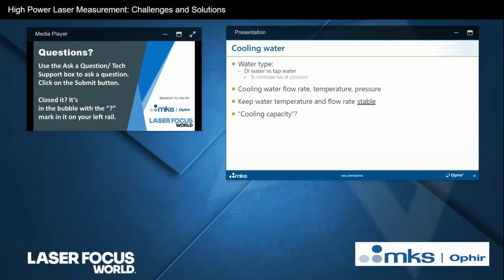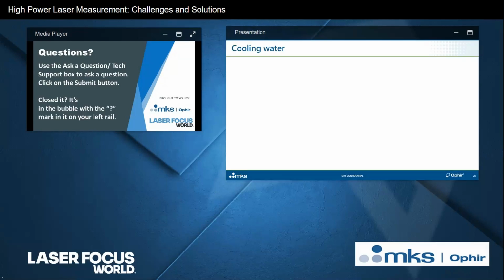I mentioned corrosion. I should just mention that Ophir offers a corrosion-proof sensor in which only copper and non-metallic materials come in contact with water. So if you have had issues with corrosion, then feel free to speak to us about that. Still on the topic of the cooling water, I mentioned earlier, I'm just going to mention it again now. Where possible, it's a good idea to have an interlock module so that it can disable the laser if it senses a sudden rise in temperature of the sensor, which is an indicator that something has gone wrong with the cooling system, and that could absolutely save the life of your sensor. As I mentioned already several times, you want to turn on the cooling water before you turn on the laser. I can't say that enough times.